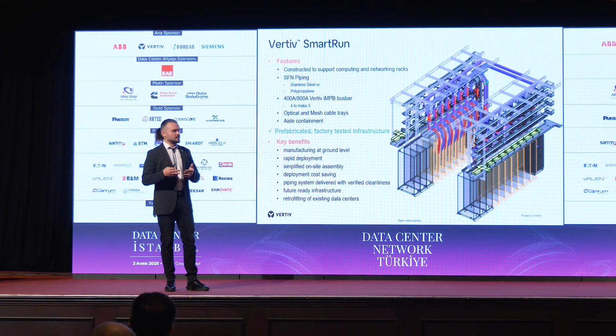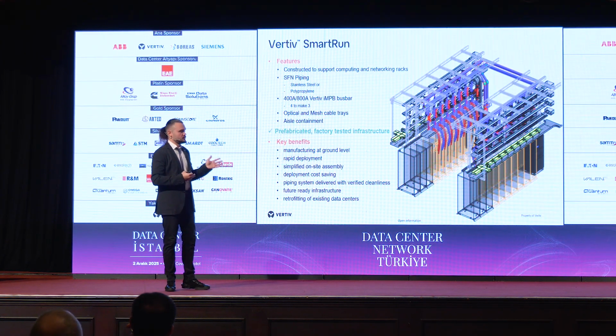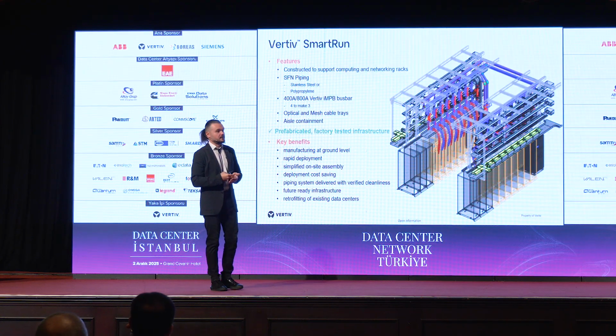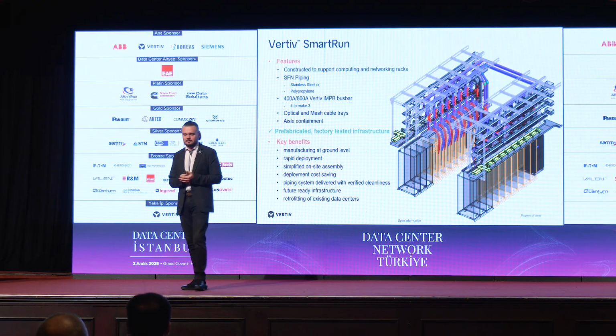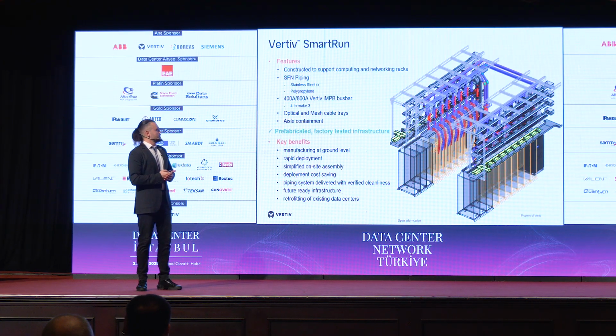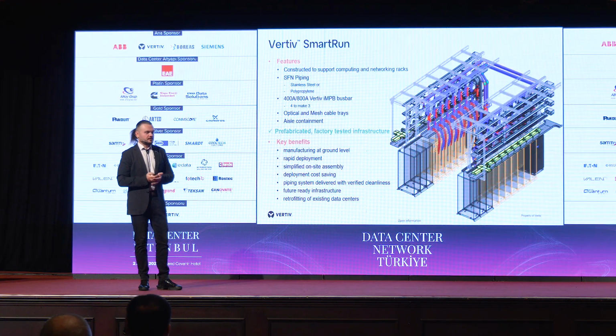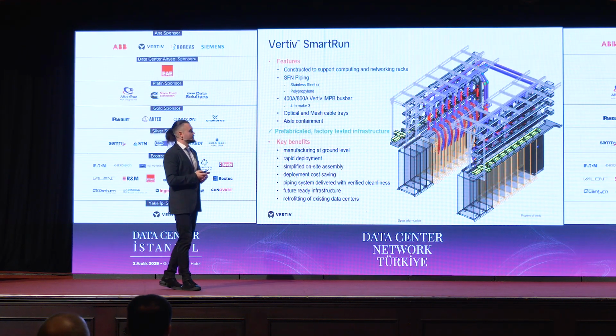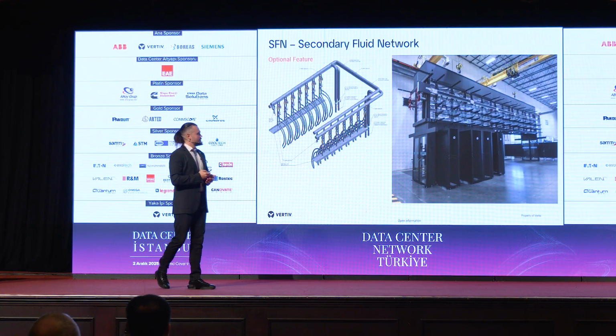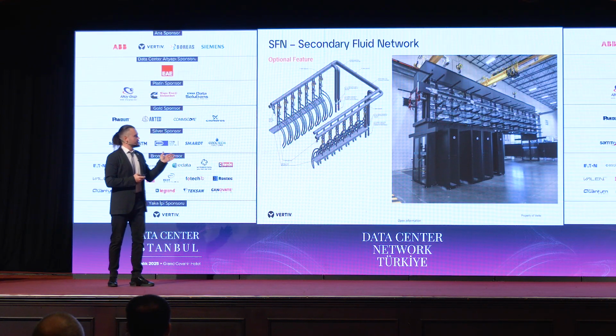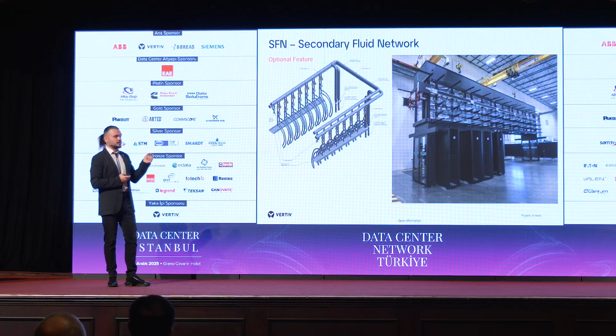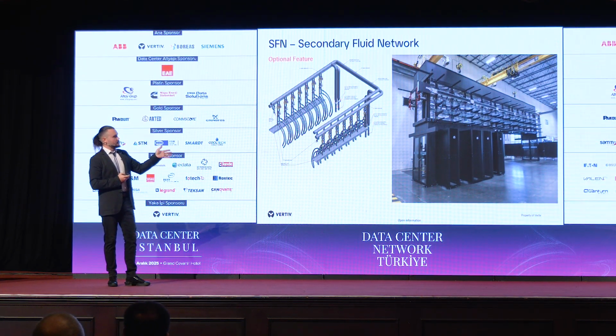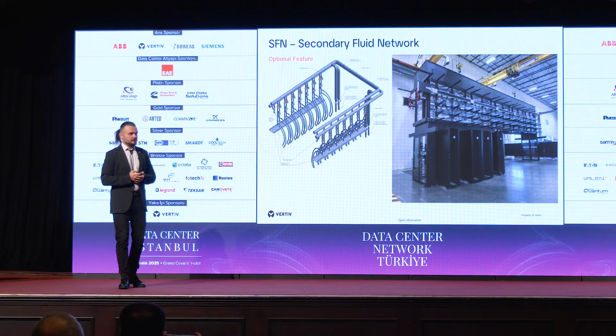As I mentioned, the topology requires 4 to make 3. Each busbar can be rated 400 amps or even 800 amps, depending on the length of the structure. And also some cable trays, of course, for connectivity. We cannot work without the connectivity. This is how the secondary fluid network looks. It's steel pipes. This is how the SmartRun looks in real life.